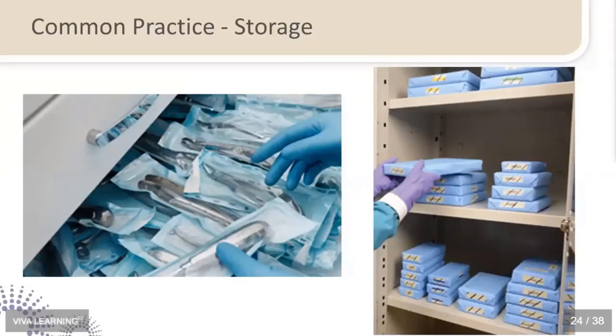So what we need to do, just like in your sterilizer, is flip them up on edge like books on a shelf, so that when you need to slide one out, you're just sliding between the two. You're not pulling it out from underneath the weight of the other cassettes. One of the things that I like on this is that piece of sterilization tape on the end where it's going to be visible. That may have a note as far as what the contents of that package are. It can also have the date of sterilization on it, and you can see by the tape there is an external exposure indicator that shows that it was in fact processed.